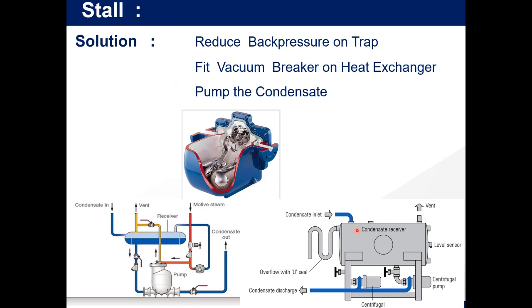And pump the condensate. So we do things like our pump traps, which here is the APT. How this works is it has a motive steam connection. So if the pressure on your inlet drops and the outlet pressure is higher, motive steam is introduced by the mechanism floating to the surface effectively and opening the port. That introduces steam into your system, making the pressure higher on the inlet, and pumps away the condensate. The other option here is a CRU, a condensate return unit. Effectively, this is a large tank with 2 electric pumps. Once this reaches a level on a level sensor, the pumps will activate and start pumping the condensate.